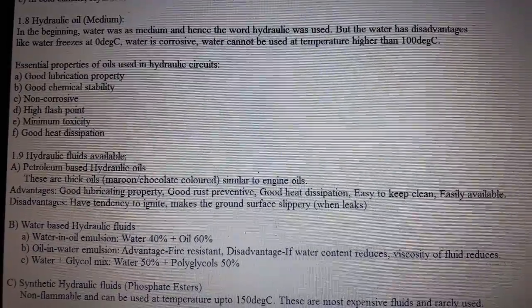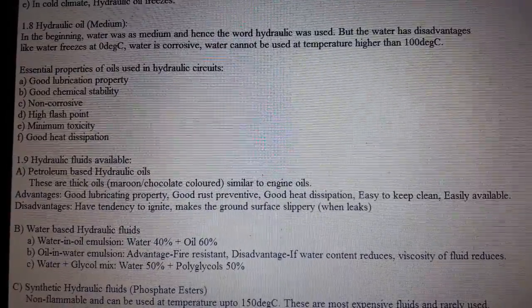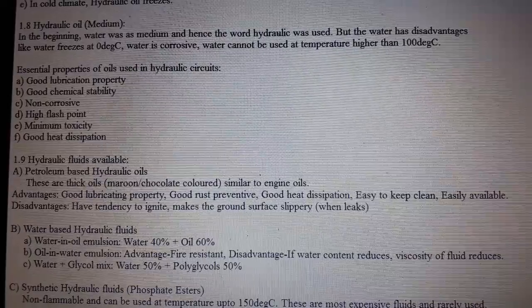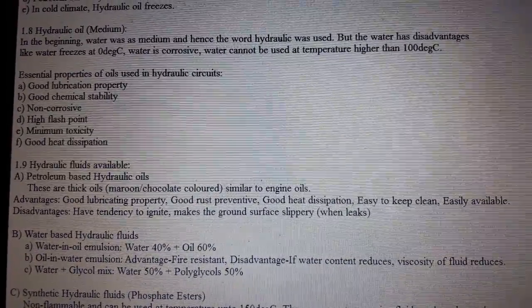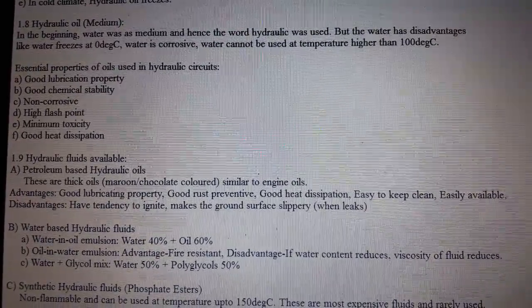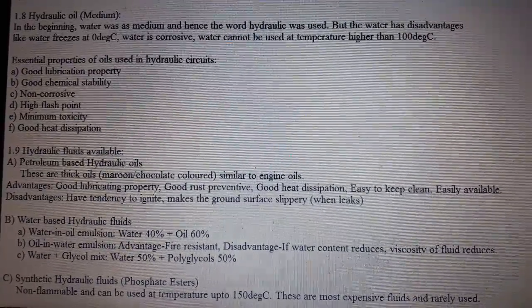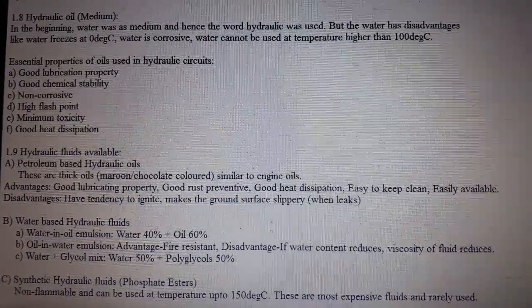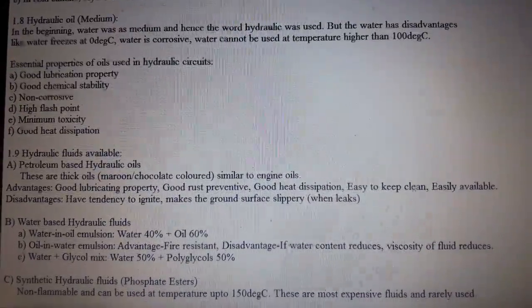Water-based hydraulic fluid: water-in-oil emulsion (water 40%, oil 60%) and oil-in-water emulsion. Advantage: fire resistant. Disadvantage: if water content is reduced, viscosity of the fluid reduces. Water plus glycol mix: water 50% and polyglycol 50%. Synthetic hydraulic fluid, i.e., phosphate esters: non-flammable and can be used at temperatures up to 150°C. These are the most expensive fluid and are rarely used.